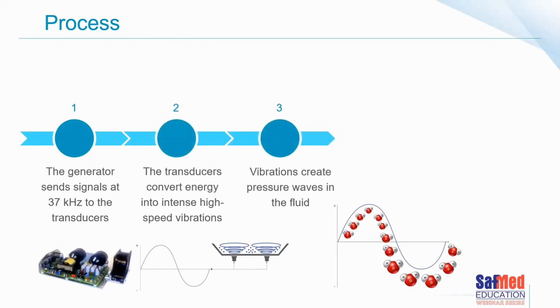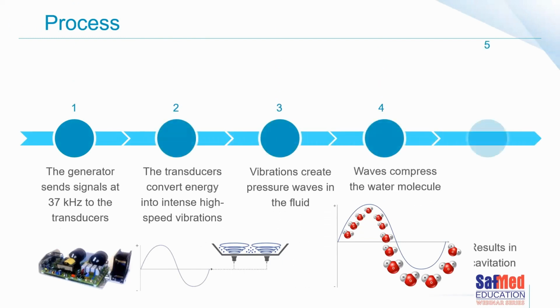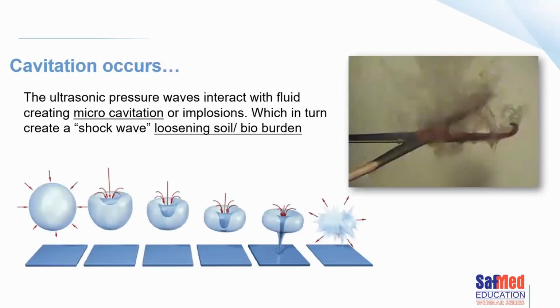The generator, as we know, will send a signal, normally at around 37 kilohertz, to the transducers. The transducers will convert the energy into intense high-speed vibrations. The vibrations will create pressure waves in the fluid. The waves will compress the water molecules, and we'll end up with cavitation. The compressed water molecule implodes. That implosion then loosens the soil or the patient debris from the instrument.